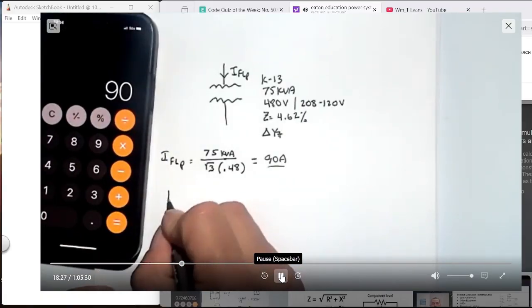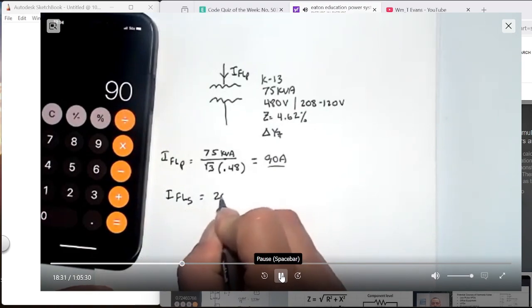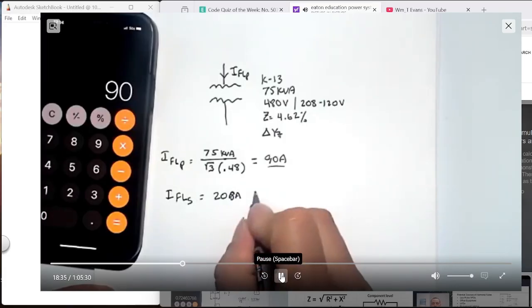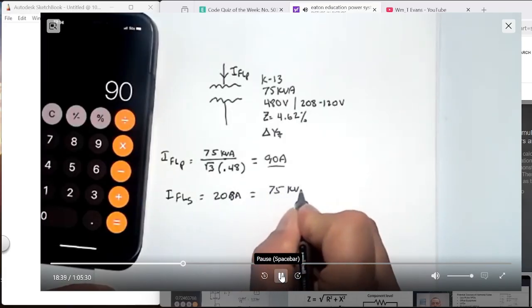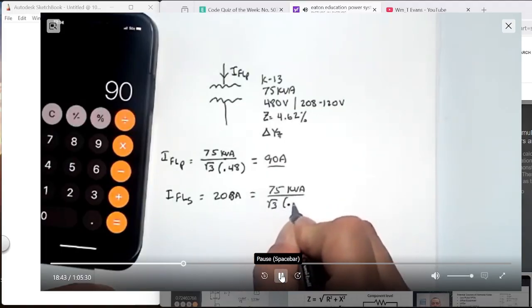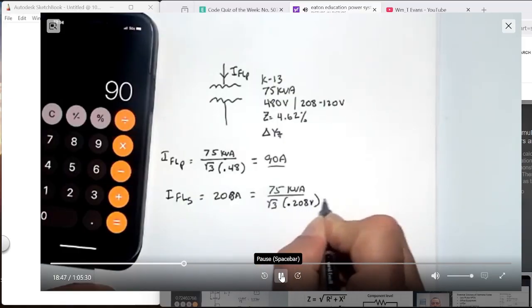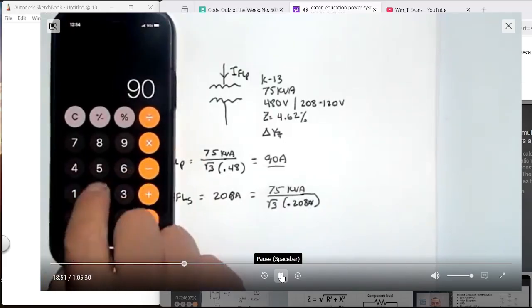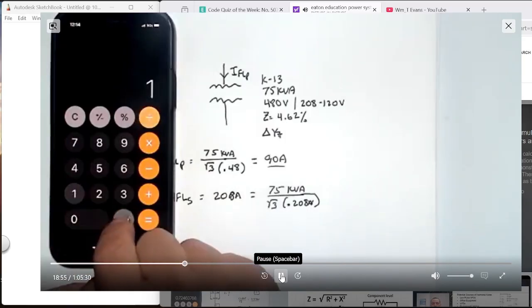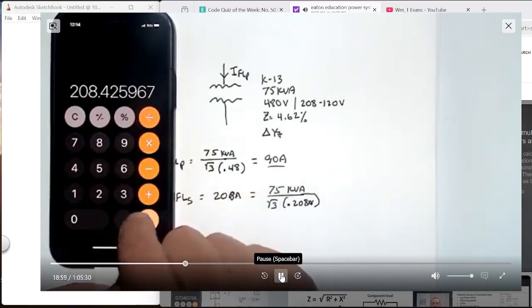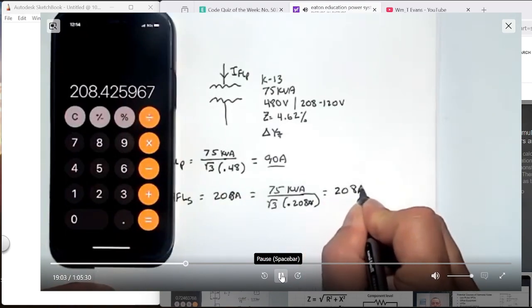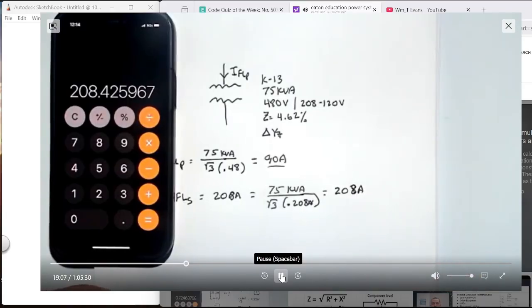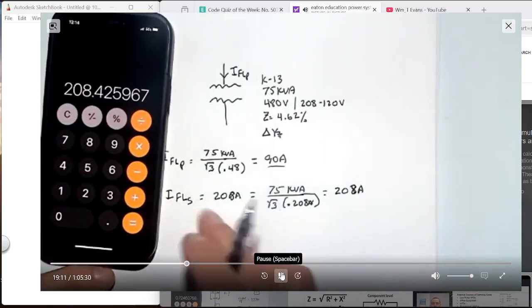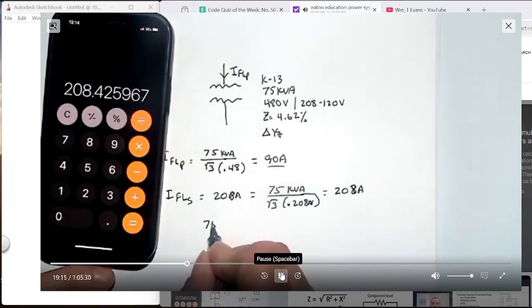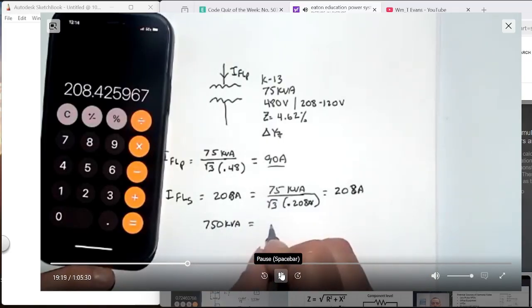Now here's the cool thing. If I want to calculate I full load secondary, I know it's 208 amps. How do I know that? Let's multiply it out. 75 kVA divided by the square root of 3 divided by 0.208 kV: 75 divided by 1.73 divided by 0.208 works out to be 208 amps. If you can remember that a 75 kVA 208 volt transformer gives you 208 amps, what would a 750 kVA transformer be? Then it's 208 times 10, or 2080 amps.